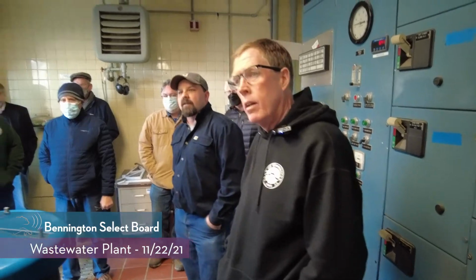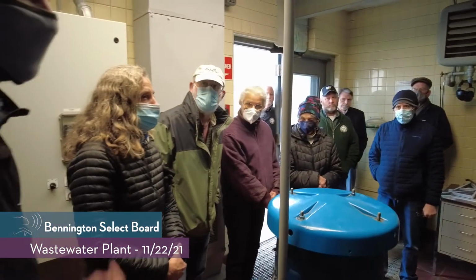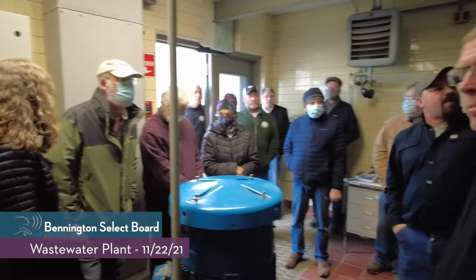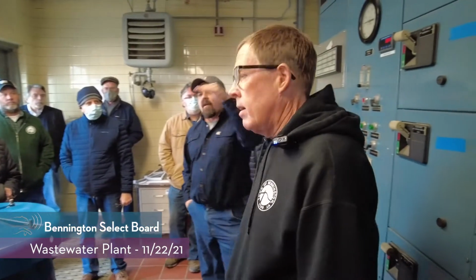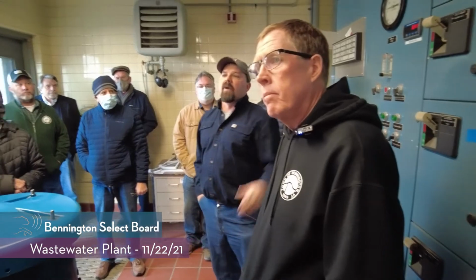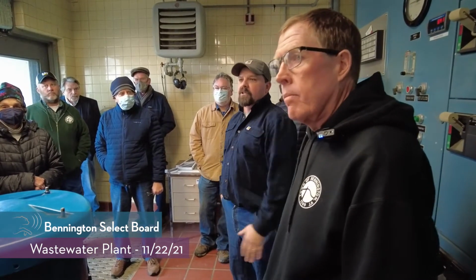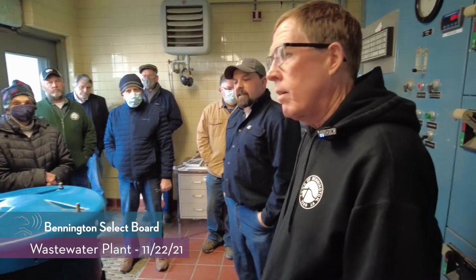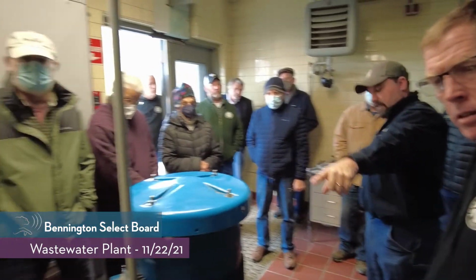And they're on a VFD? Yeah, they're all on VFDs. They run on the wet well level, so they ramp up and down accordingly. If it gets too high, the lag will kick on. When it gets to a nice level, the lag will shut off. That one's actually out of commission. There's a drive shaft that goes 2 stories down.